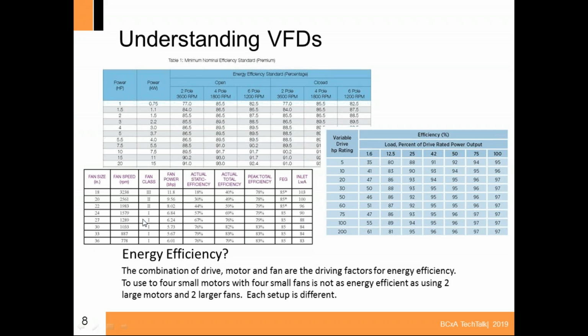Then we can come back over here and look at fan classes and see how they operate. We have fan speed and RPMs over here on the right, and as you can see, the bigger the fan, the more static and total efficiency we gain. So we actually have a better performing fan. So when I talk about energy efficiency, I can tell you that four 1 horsepower motors with 18-inch fans are probably not as efficient as two 2 horsepower motors with 22-inch fans, just because of the nature of how all these come together.